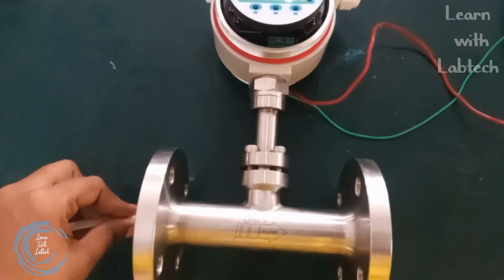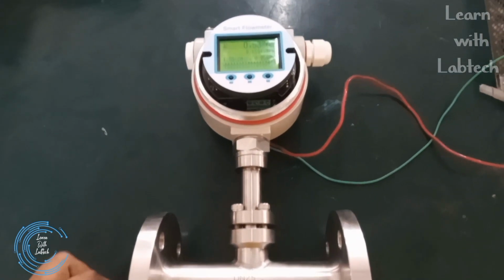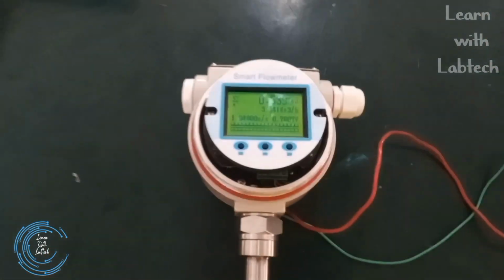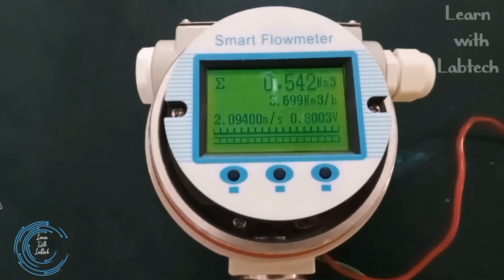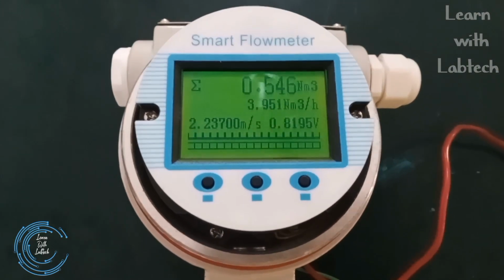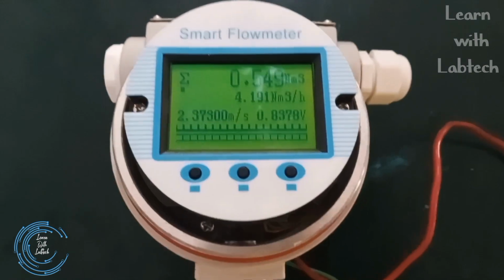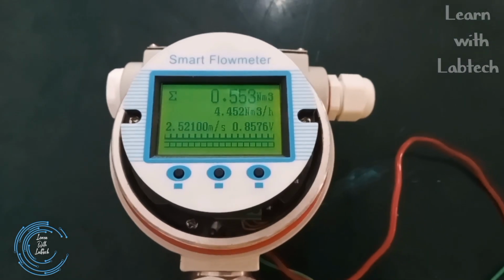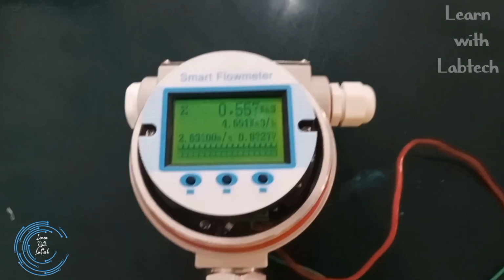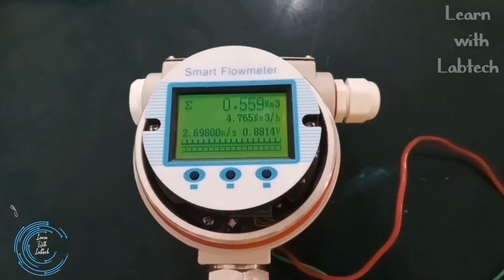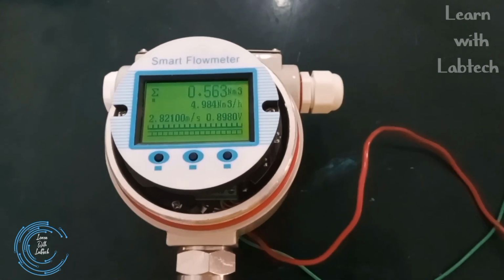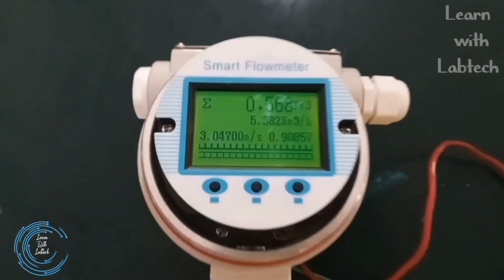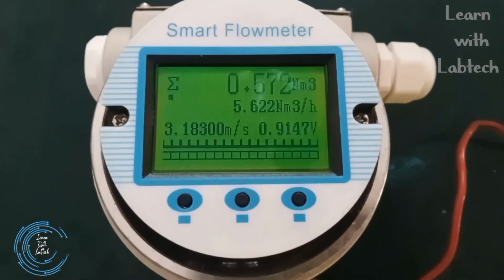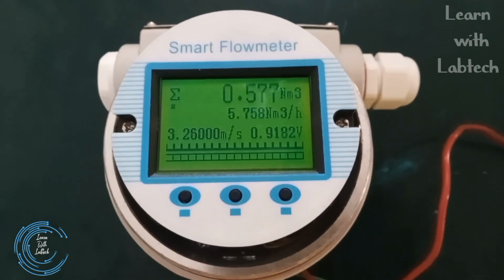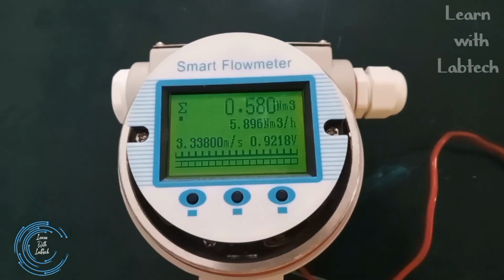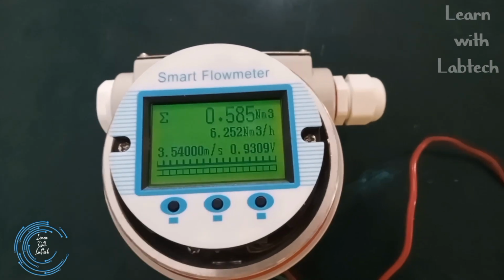Let's check with compressed air. We are testing with compressed air. You can see the changes here. In instant flow, it gradually changes. The compressed air given is 20 psi. You can see the changes. 5.6 normal meter cube per hour. Velocity 3.4 meter per second.